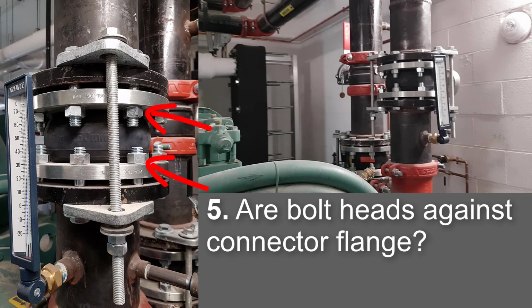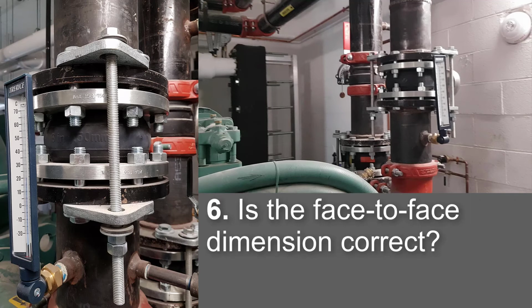Are the bolt heads against the connector flange? Nope, just as before, the bolts are backwards. But also as before, I found no damage to the bodies of the joints, so there's no need to ask the contractor to fix this. We'll call this one close enough. Is the face-to-face dimension correct? I didn't measure these, but probably should have at least measured the second one. Neither one looked excessively stretched or squished, so I think I'll call these close enough, and okay as well.